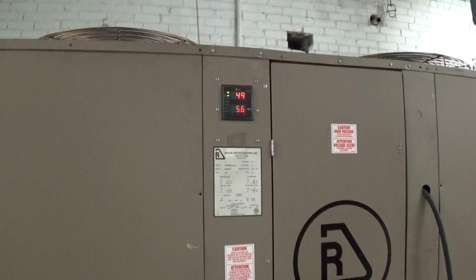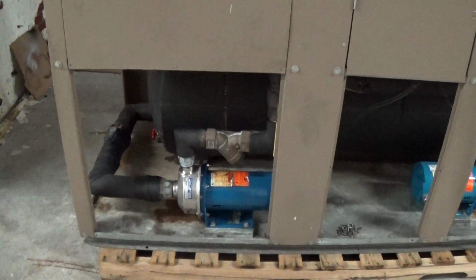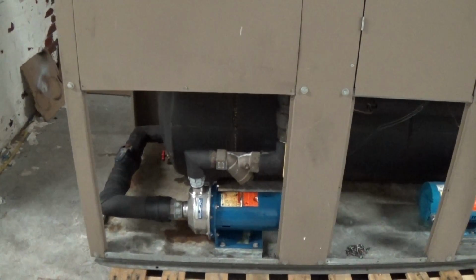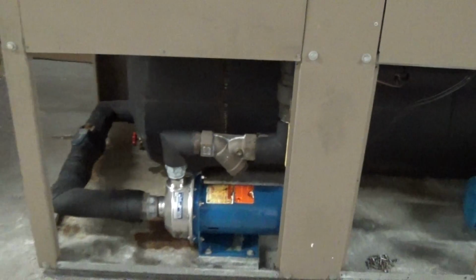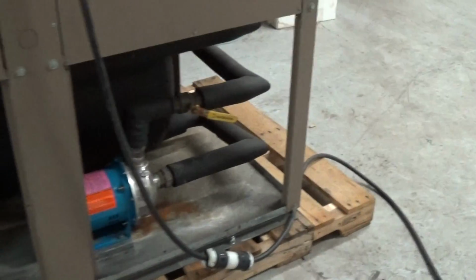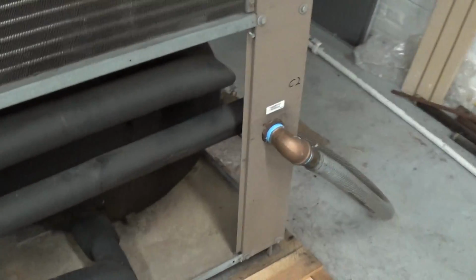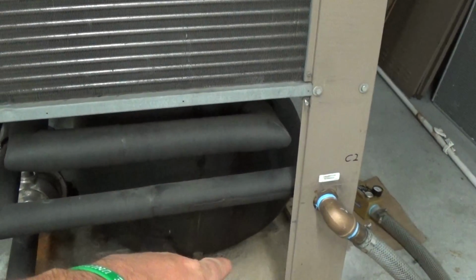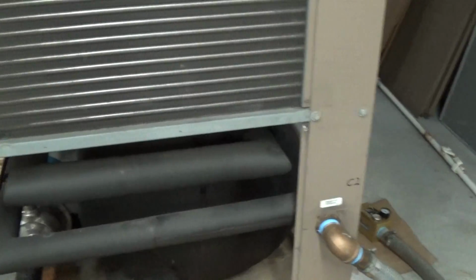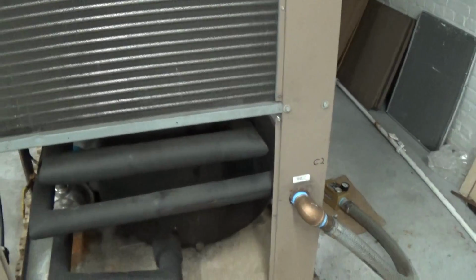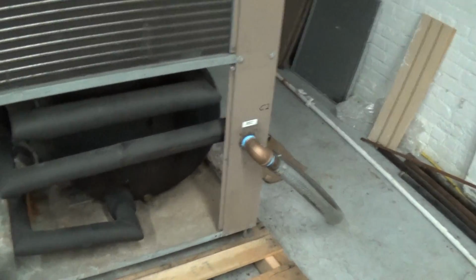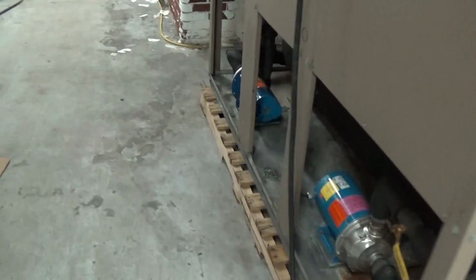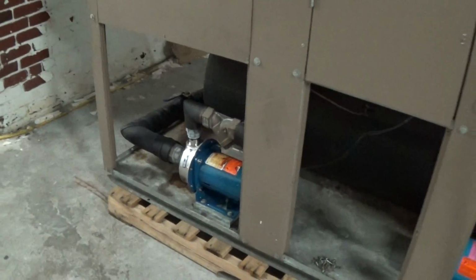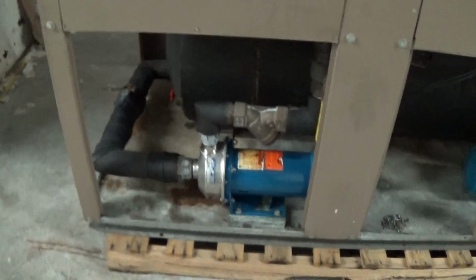Now with this chiller, because it has your circulation of the evaporator pump, the whole issue of having a bypass on your exterior piping kind of goes away. Usually the reason for having a bypass line between your inlet and your outlet is to make sure you have proper flow over your heat exchanger all the time. Because this is a 2-pump system with the evaporator pump here, that kind of eliminates that need.